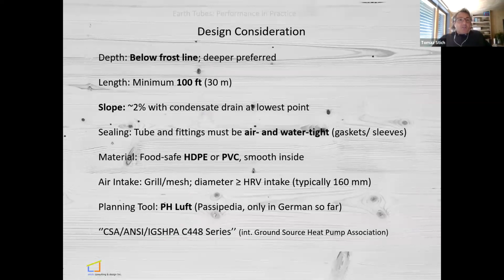The depth of your earth tube should be below the frost line. Deeper preferred, of course. Ours starts at 10 feet and then slightly slopes up. The length should be minimum 100 feet. Slope around 2%, so that in summer the water can run down to the lowest point where it can be released through the P-trap.